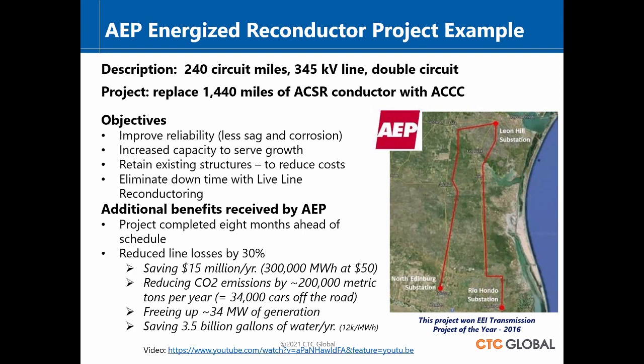So they decided to use the existing towers and put ACCC up instead. To avoid taking an outage, they used a company that did live line reconductoring — they literally handled high voltage, brought a line down, put it on a pole next to the towers, put new line in, electrically cut it over, and repeated the process. They did that in 9 segments.